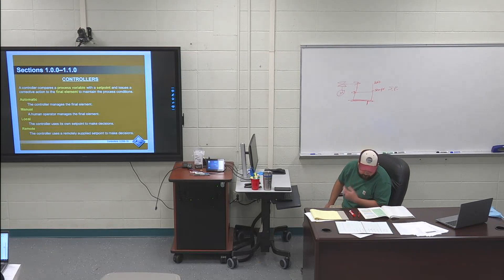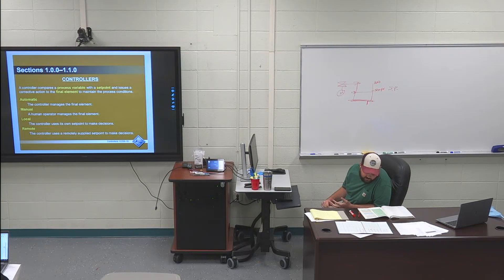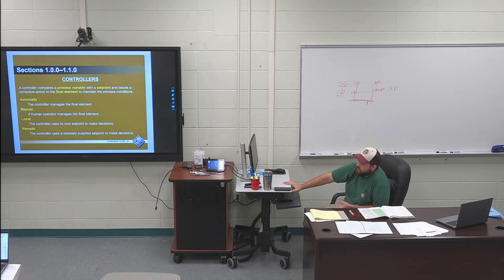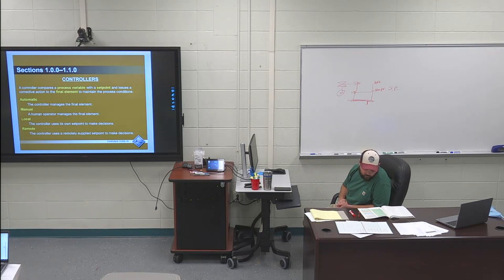I've got local control highlighted — third bullet point, first two sentences. 'When a controller is in local control, the set point comes from a set point adjustment located on the controller itself. The only way to change the set point is to manually change it with a set point adjustment.' That's like the PID controller some of you worked with this semester — it's local to what you're controlling, not in a remote control room.